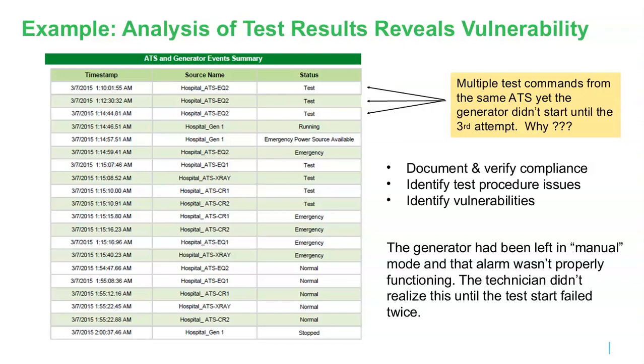And so what this really identifies by having this sequence of events is whether or not your system is not only performing according to the standards, but do you have the awareness of your vulnerability? So in this case, the generator was in manual, and yet the facility didn't have the alarm enabled so that they would be able to know that.